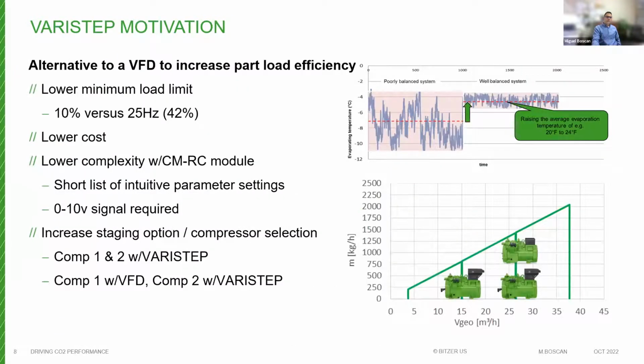Circling back to VariStep, with the release of VariStep with the TE compressors, BITZER offers a low-cost, simple solution in the form of mechanical capacity regulation. This, in conjunction with the CMRC IQ module, has the potential to operate as low as 10% of the full load capacity in the stepless mode. VFD operation is limited to 25 hertz, or about 40% of the full load capacity.